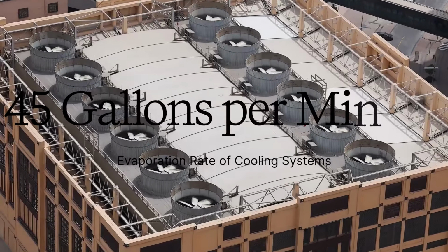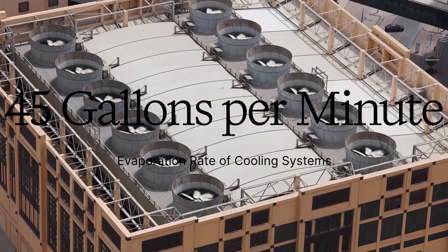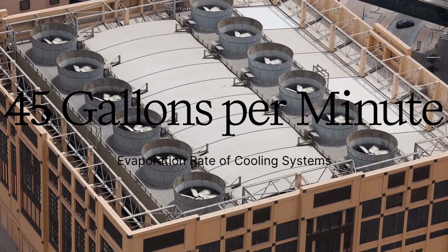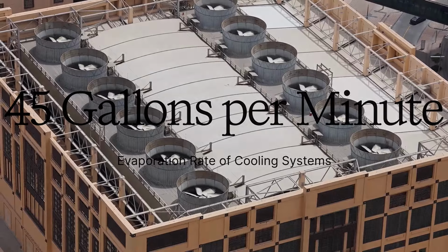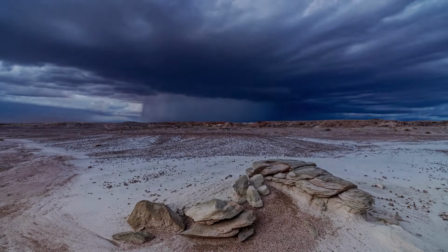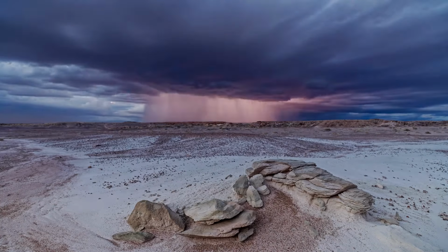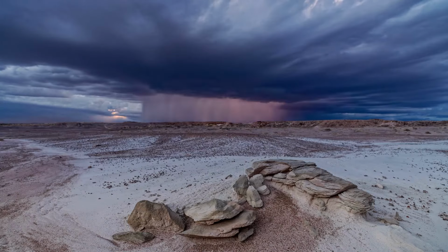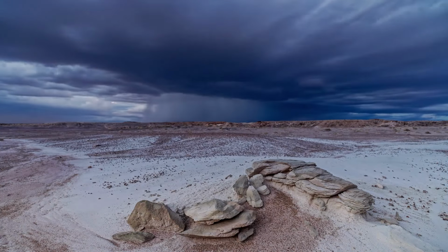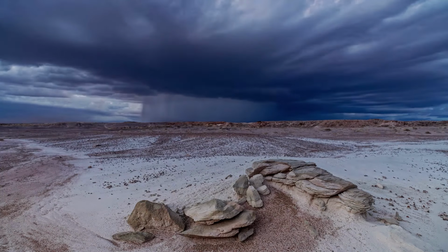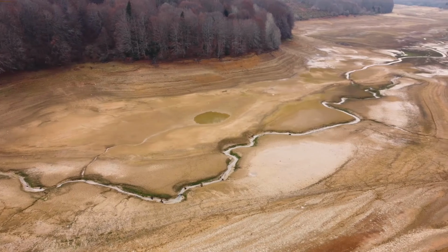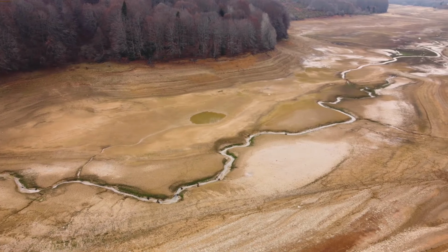For a typical 1,000-ton cooling system running continuously, about 45 gallons per minute evaporates into the atmosphere. Those water molecules leave the local watershed. They become vapor that might precipitate hundreds or thousands of miles away. It isn't lost completely to nature, but it might fall into a source that's not clean, like the ocean. So from the perspective of the river or aquifer you drew from, that water is gone.